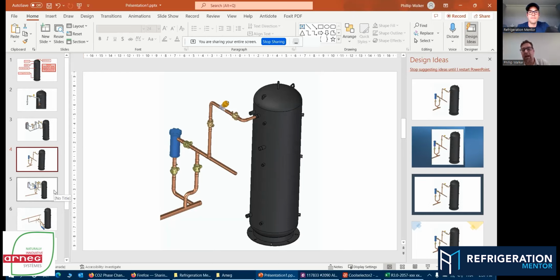Rule of thumb: if you're doing a big renovation, really look at your liquid side and put some HH filters in there. CO2 and humidity don't go very well together, as I think everyone has seen. So a good cleanup filter is always recommended throughout a renovation. But besides that, Trevor, it's run of the mill. After we do startup, we recommend a filter change with the first oil change. We recommend the oil change not be just a rule of thumb for when to do it. We like an oil test.